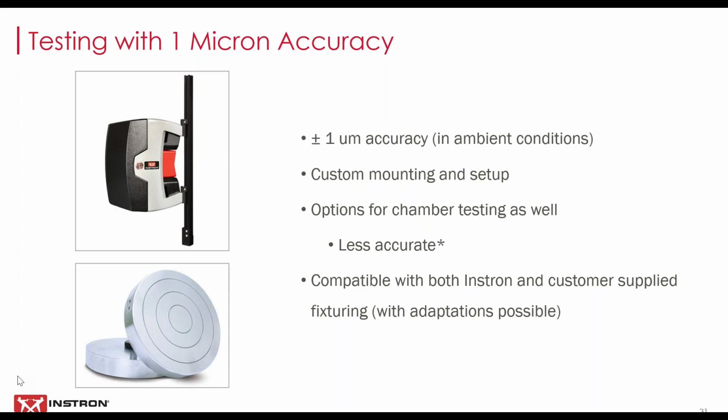It's a little easier because in tensile testing, usually your specimens are a lot larger. But what we've seen in the electronics industry lately is a lot of these specimens might be a millimeter tall, or some are in the realm of 80 to 100 microns when you're talking about battery materials and testing. So being able to compress those and get a proper accuracy that actually is a small amount of error versus a larger amount of error is pretty critical here.